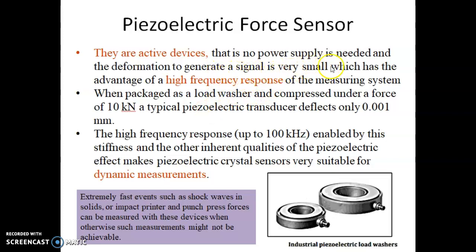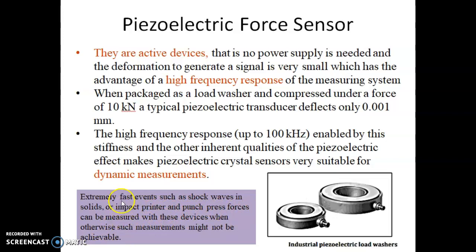The generated signal is very small but has the advantage of high frequency response. These instruments are used for high frequency responses up to 100 kilohertz, making them suitable for dynamic measurements such as shock waves in solids, impact printers, or punch press forces.